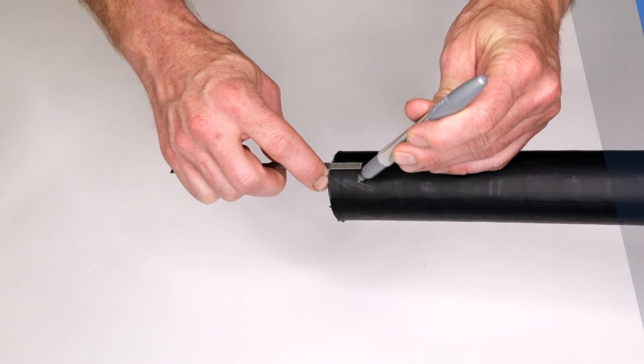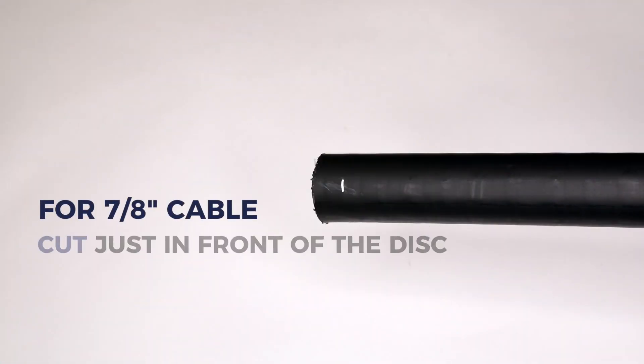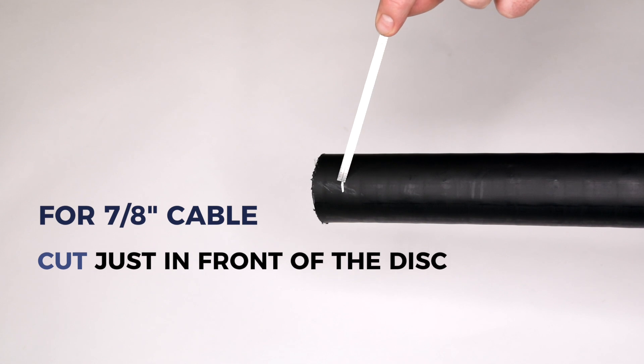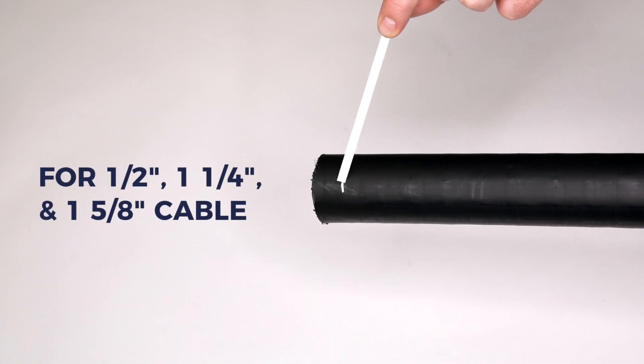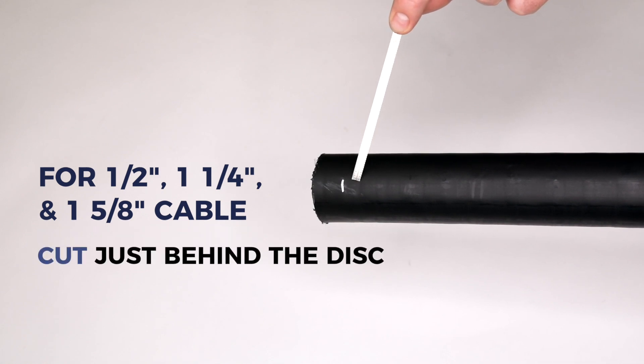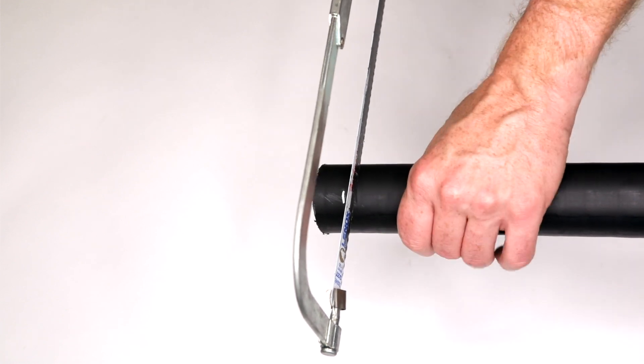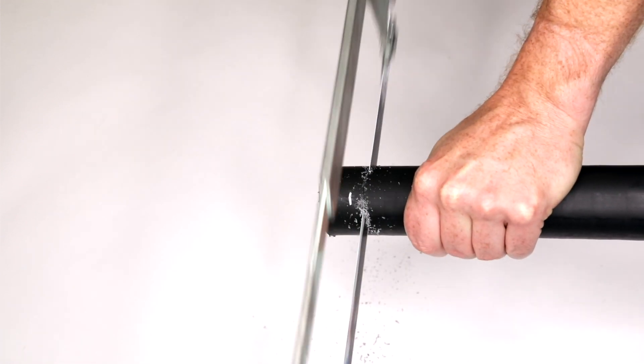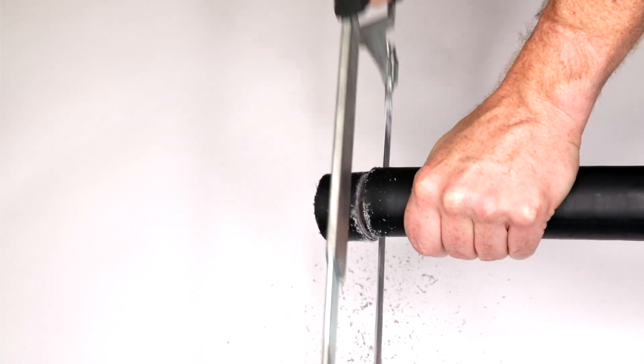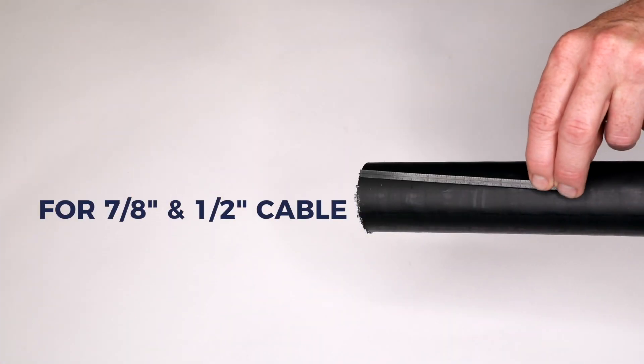For 7/8-inch cable, cut just in front of the disc. For half-inch, 1-1/4-inch, and 1-5/8-inch cables, cut just behind the disc. Cut the cable squarely using a hacksaw. Ensure that the cable is straight for at least 10 inches from the end for 7/8-inch and half-inch diameter cables.